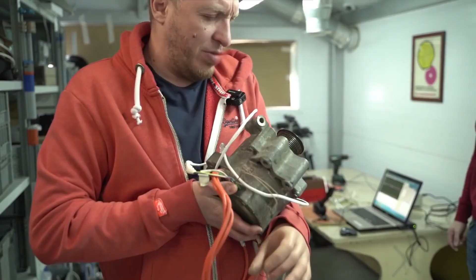It also has a resolver, as far as I understand. And a resolver is much better than Hall sensors, right? Yeah. The resolver, first of all, inherently gives you an absolute value, and secondly it possesses a high resolution. Because of this, at any given moment, even with a real physical motor, we can precisely know the rotor's position, and accordingly we can accurately form the magnetic field exactly for the correct torque.